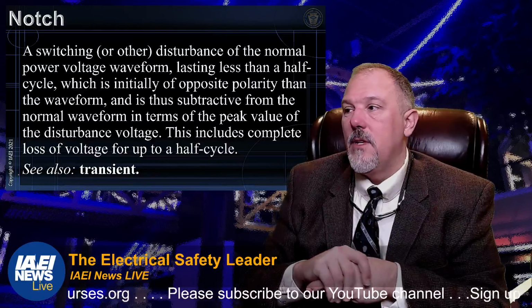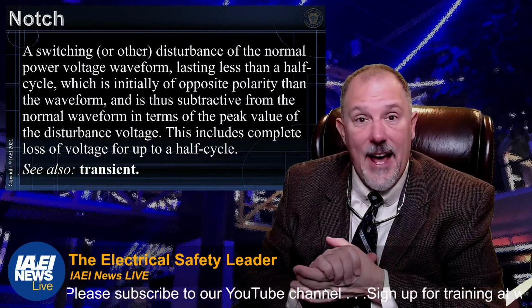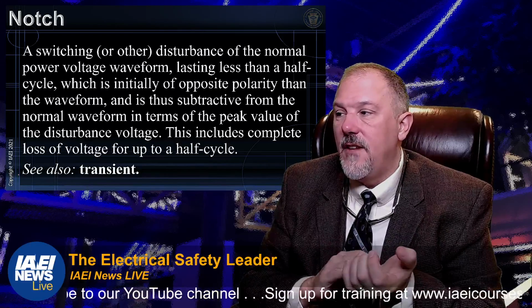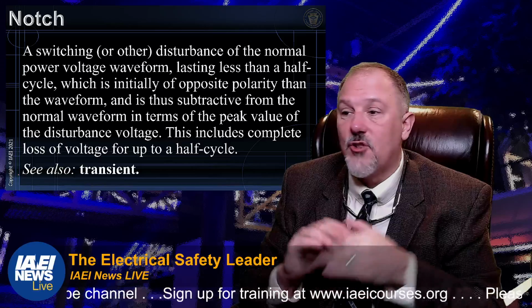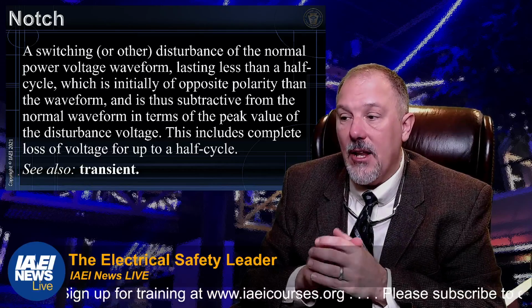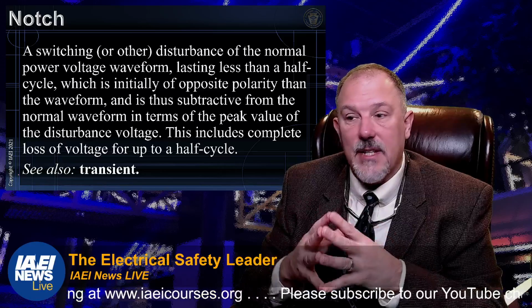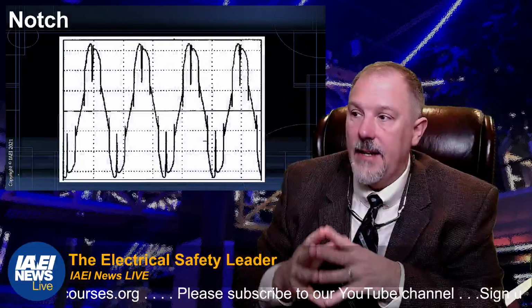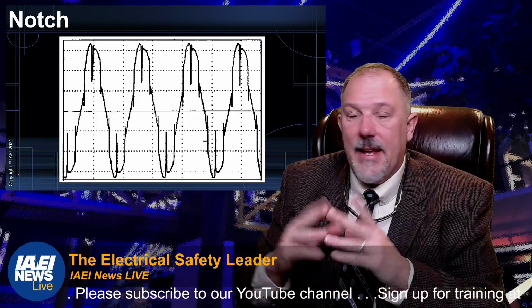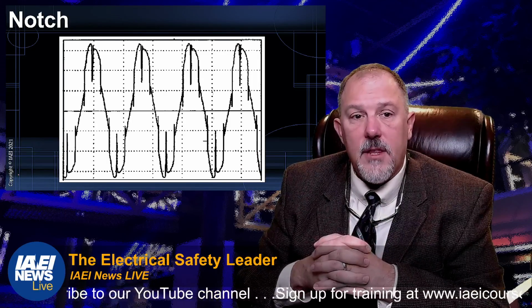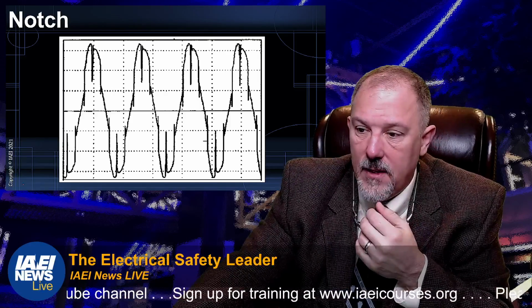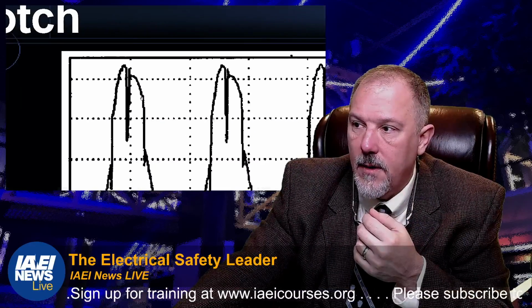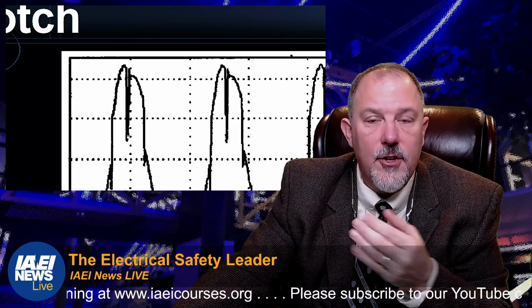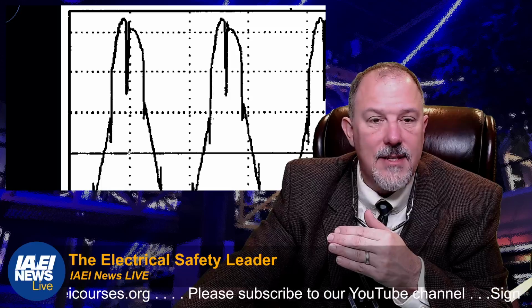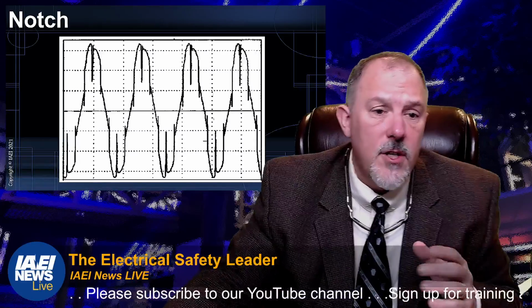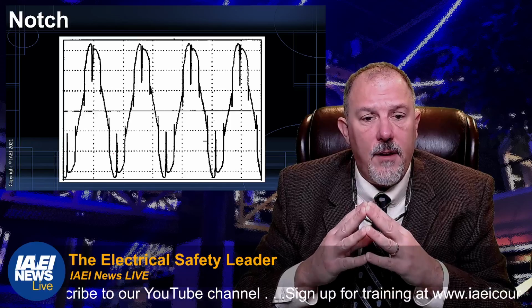Now, a notch is a disturbance lasting less than a half cycle, which is initially of opposite polarity than the waveform and is subtractive from the normal waveform. It includes complete loss of voltage for up to a half cycle. That is a notch. I got a little picture of that here. And that's an ugly looking waveform, but those are notches. What you'll see, let's try to zoom in. Okay, that is a notch that occurs, and it could go down to 0 volts, all the way down to this line here. Those are notches. So you have a notch, which is a voltage event as well.